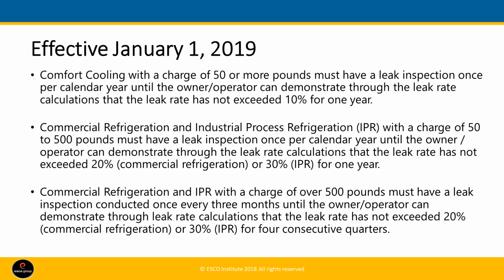With a system that has over 500 pounds of refrigerant, the leak inspection must be conducted every 3 months until the owner or operator can demonstrate that the leak rate calculations have not exceeded the leak rates for 4 consecutive quarters. So in the systems holding a large volume of refrigerant, it's got to be checked 4 times in a row within the year to make sure that it's not leaking.